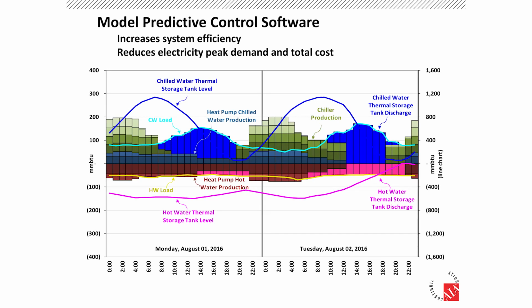This is the model predictive control software. When we came up with the scheme, we realized we want to deploy these five basic components for an energy system for a campus: heat pumps that do both heating and cooling, chillers that do just cooling, hot water generators that just do heating, and hot and cold thermal storage. You have these five major components, and trying to figure out how to use all of them in the best way was the engineering challenge.